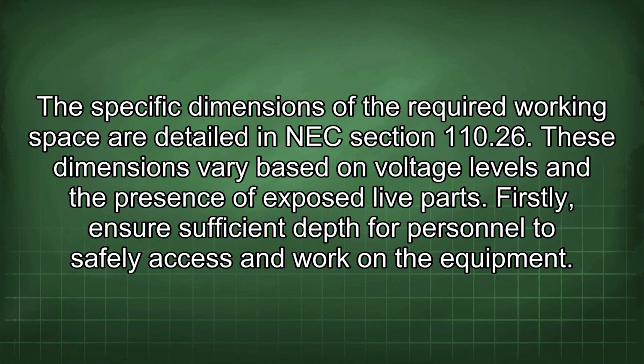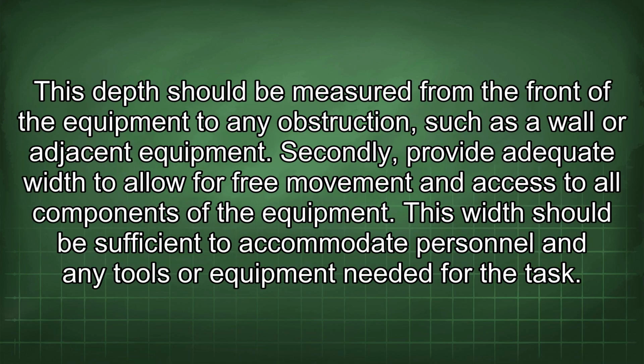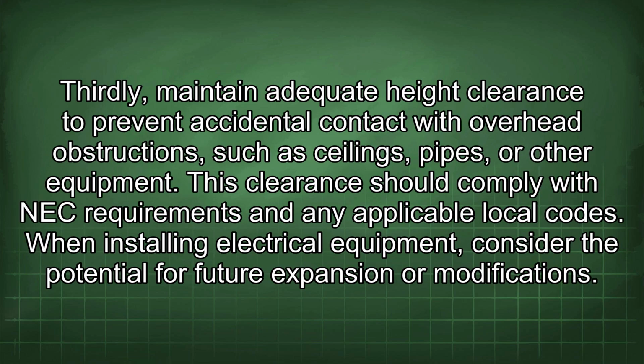Firstly, ensure sufficient depth for personnel to safely access and work on the equipment. This depth should be measured from the front of the equipment to any obstruction, such as a wall or adjacent equipment. Secondly, provide adequate width to allow for free movement and access to all components of the equipment. This width should be sufficient to accommodate personnel and any tools or equipment needed for the task. Thirdly, maintain adequate height clearance to prevent accidental contact with overhead obstructions such as ceilings, pipes, or other equipment. This clearance should comply with NEC requirements and any applicable local codes.